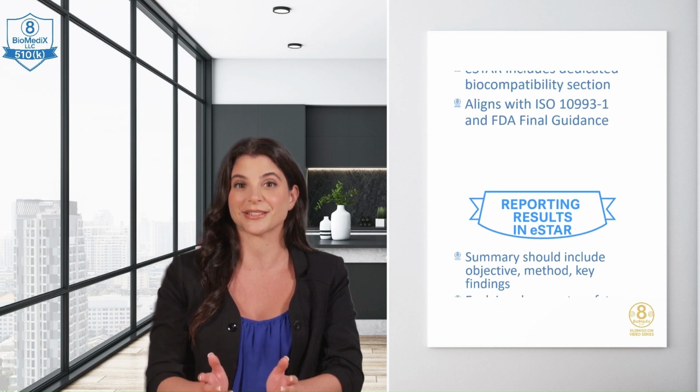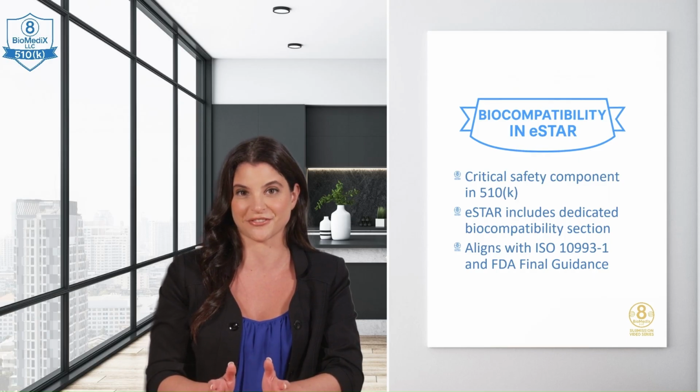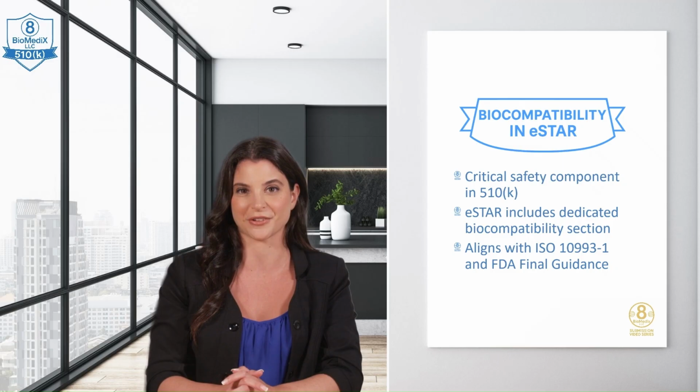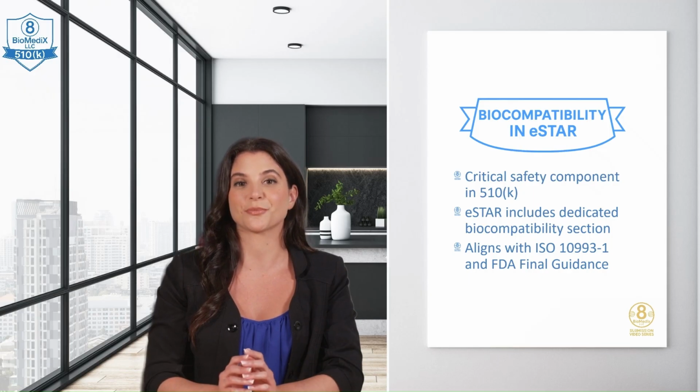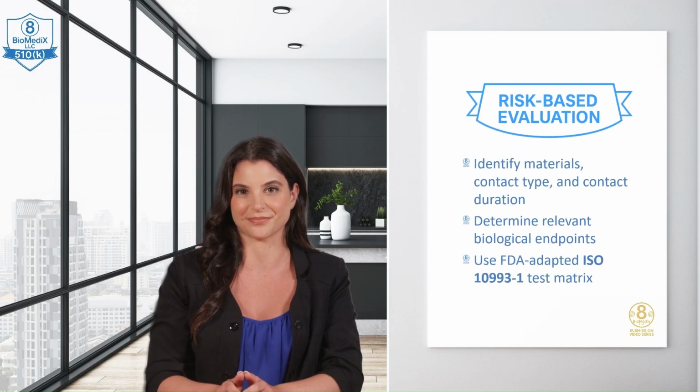Biocompatibility. Now, let's talk about biocompatibility, one of the most critical safety elements in your submission. And yes, eSTAR has a dedicated section for it, aligning perfectly with ISO 10993-1 and the FDA's final guidance for U.S. submissions. Risk-based evaluation. Biocompatibility begins with a risk-based evaluation. What materials contact the body, for how long, and in what way?